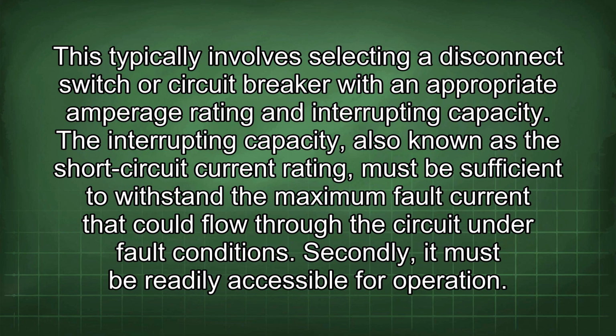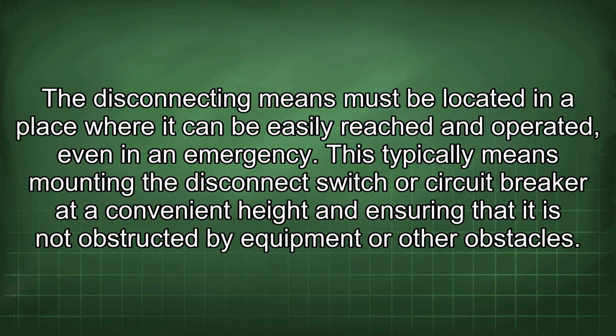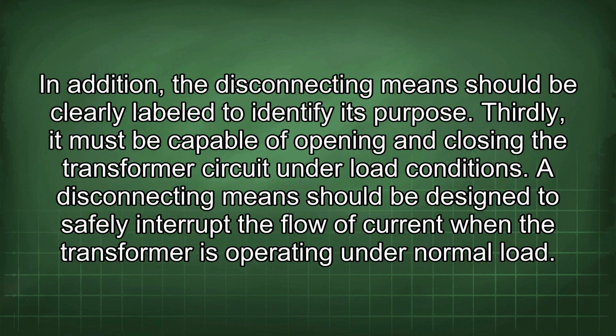Secondly, it must be readily accessible for operation. The disconnecting means must be located in a place where it can be easily reached and operated, even in an emergency. This typically means mounting the disconnect switch or circuit breaker at a convenient height and ensuring that it is not obstructed by equipment or other obstacles. In addition, the disconnecting means should be clearly labeled to identify its purpose.